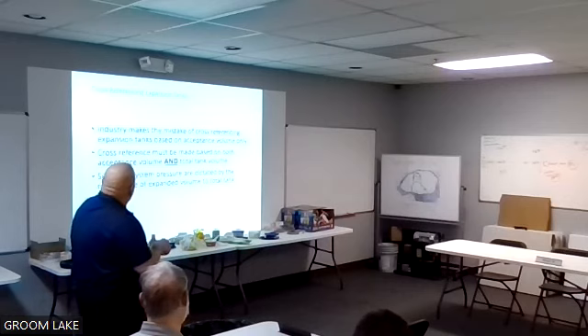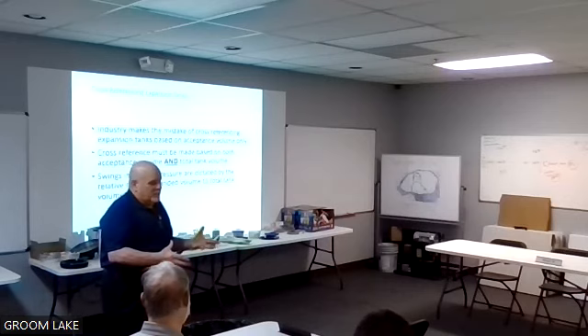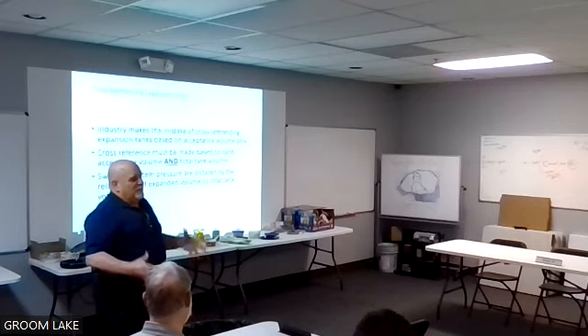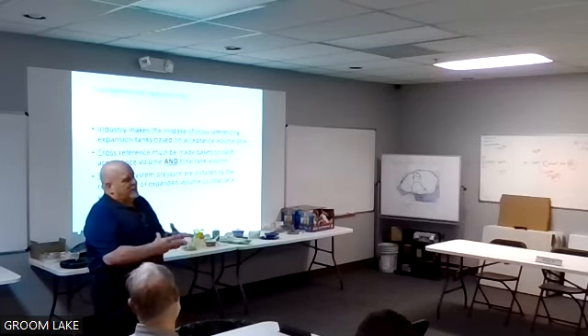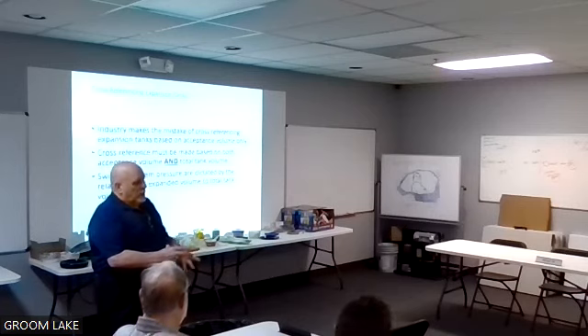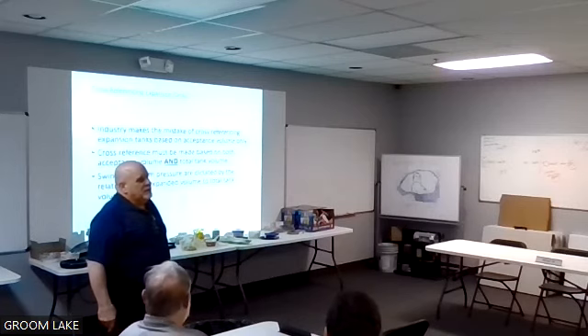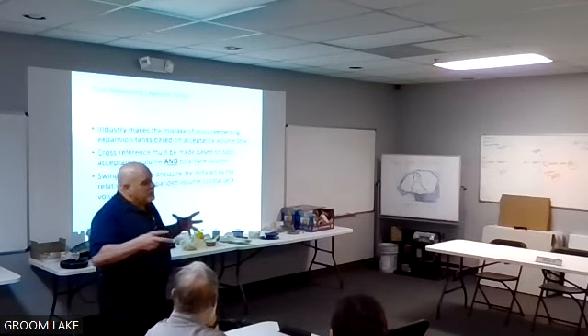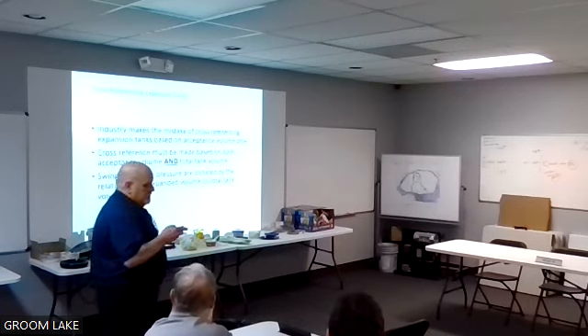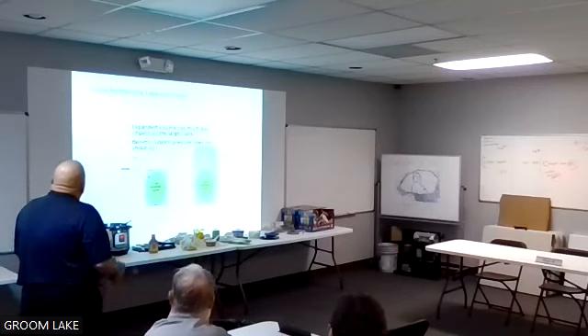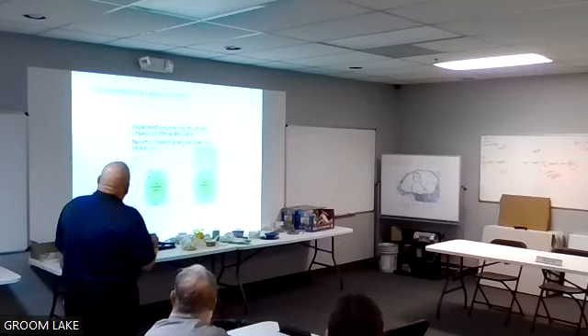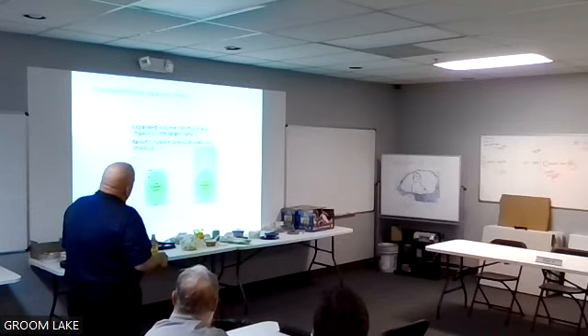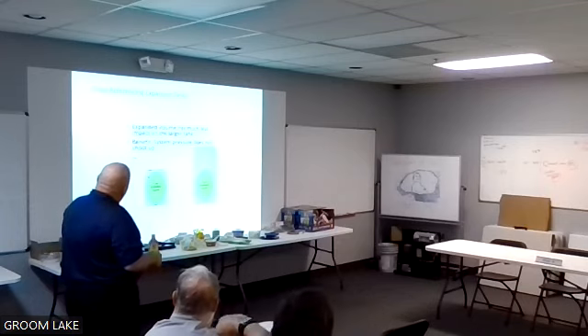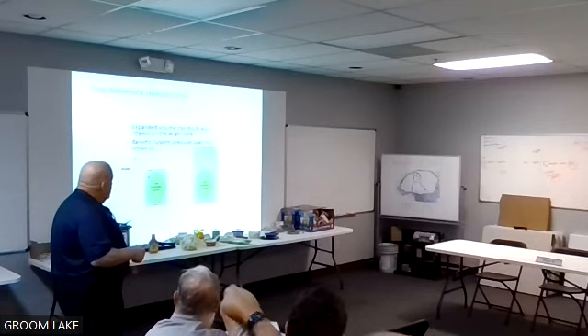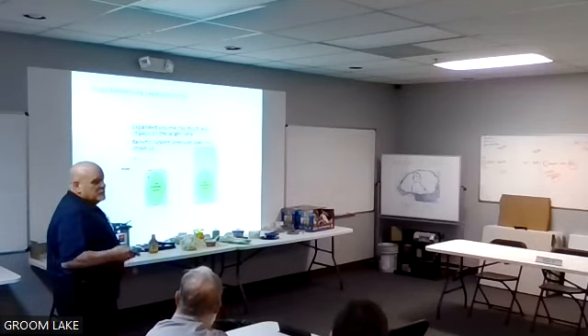And swings in pressure are dictated by the relative size of the expanded volume. That's why you have to be careful how big my acceptance is and my volume. I have to have enough volume to compress to work correctly. If I'm short air charge, I'm going to lift the relief valve. I have to have enough room to compress and make that look right. So just expanded volume, like I said, 5-gallon. This is your bladder. This is your whole tank. This is a full bladder. You've got to know what both those are.